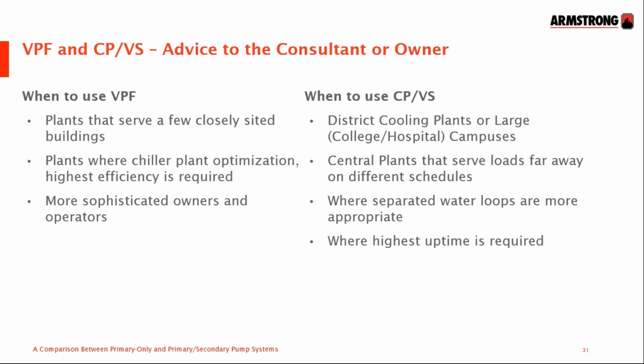So what happens if an engineer or an owner asks you which type to use? Well, they both have an application, so we're not going to denigrate either side. They both have their strengths and weaknesses. Variable primary flow is suitable for either a single building or a few closely sited buildings of similar size, where load variation is not going to be extreme, where highest efficiency is required, and where you know they're going to have a good quality maintenance team behind them. Constant primary, variable secondary is best for big systems, wide-ranging systems across a large campus, be it hospitals, colleges, universities, military bases. They're going to be where you have diverse loads that can come on at different times and change dramatically. So that's where you want constant primary, variable secondary.